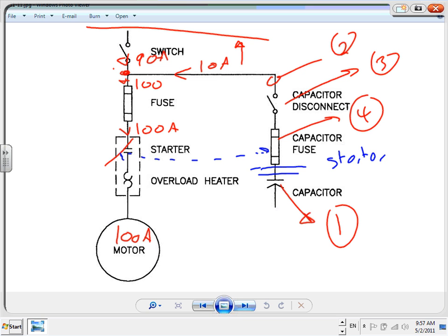You can see it. These two are local correction, or one is global, right at the switchgear. Is there a better way? This is the better way. Cost effective is different. This is more expensive, better way. Correcting at the switchgear is less expensive, but you're taking a chance.